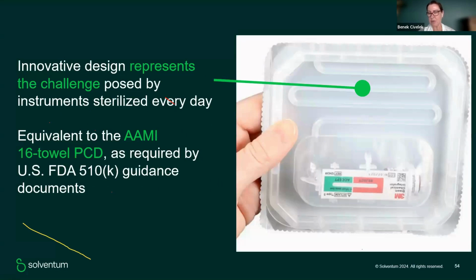So again, whenever we put it inside, we expect first, with the vacuum, the air should be out of the chamber, out of the load, and at the same time out of this PCD. And with the quality steam injection, we expect the steam to reach through this channel and the moving color technology type 5 indicator, and also the PCD containing the biological indicator. Again, this is, of course, FDA cleared and always equivalent to the AAMI 16 towel pack.